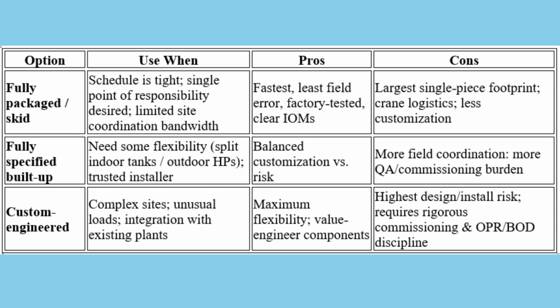Decide which option to buy. A fully packaged skid is best when schedule, quality control, and a single point of responsibility matter most. It arrives factory assembled and tested, then connects to building water, power, and anchors. A fully specified built-up system mixes vendor components but keeps one provider accountable for the set. It offers flexibility with moderate risk. A custom-engineered plant fits unique sites and complex retrofits, but demands rigorous QA and commissioning. If your team is new to central HPWH, start with a packaged skid or a single vendor built-up approach.